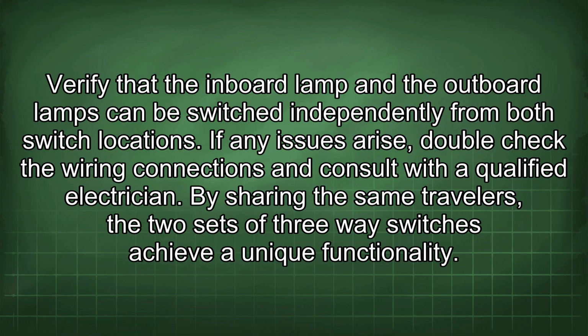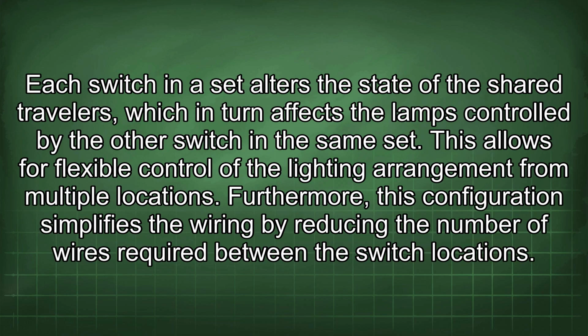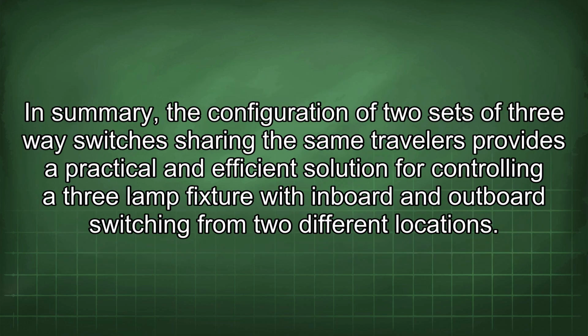By sharing the same travelers, the 2 sets of three-way switches achieve a unique functionality. Each switch in a set alters the state of the shared travelers, which in turn affects the lamps controlled by the other switch in the same set. This allows for flexible control of the lighting arrangement from multiple locations. Furthermore, this configuration simplifies the wiring by reducing the number of wires required between the switch locations. In summary, the configuration of two sets of three-way switches sharing the same travelers provides a practical and efficient solution for controlling a three-lamp fixture with inboard and outboard switching from two different locations.